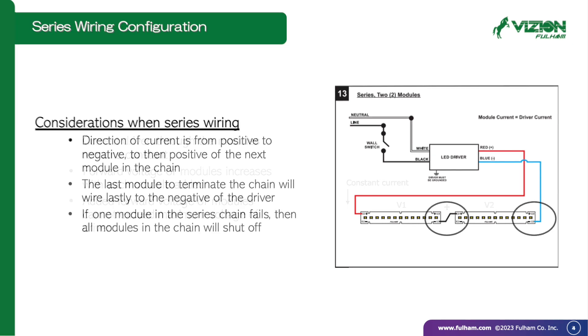Wiring will be done from positive of the driver output to positive of the first module in the chain, then negative from the first module to the positive of the second. This chain will continue until the last module, in which the negative of that module will return to the negative of the driver.